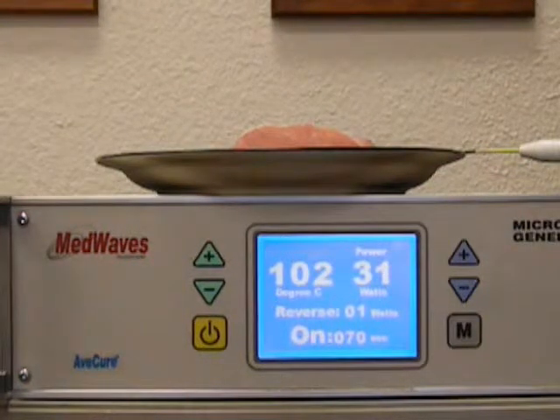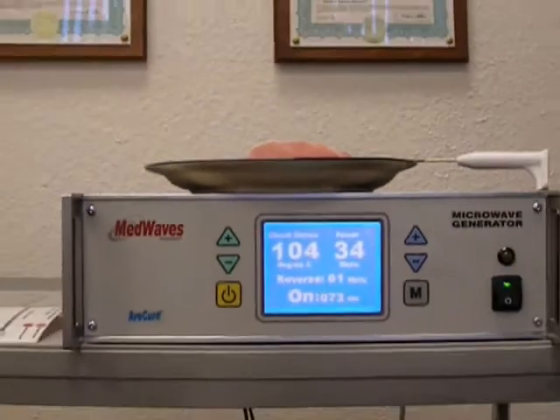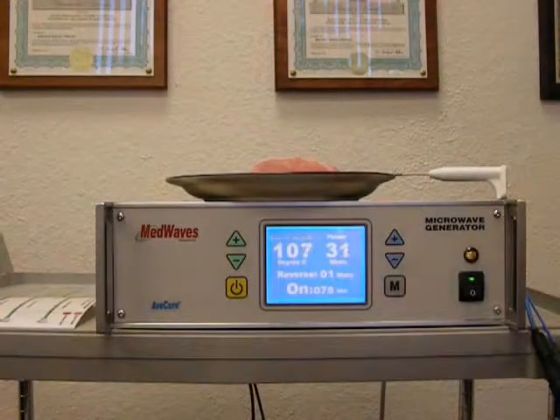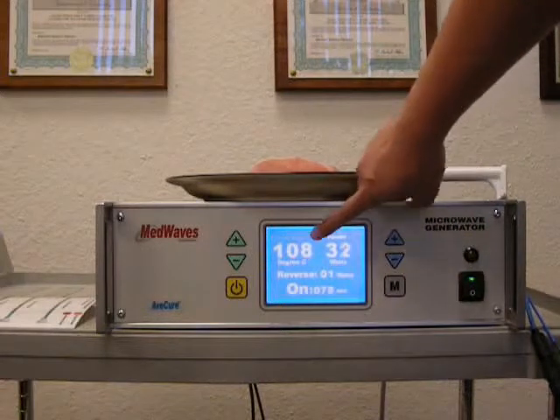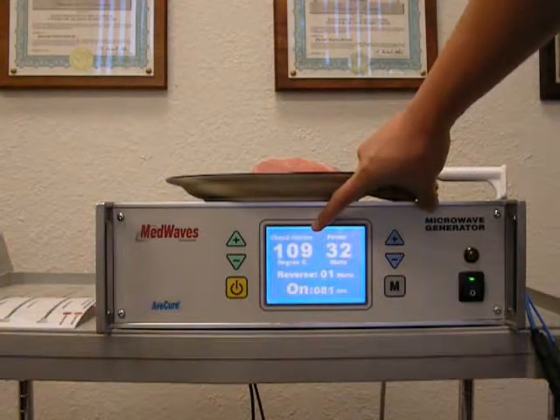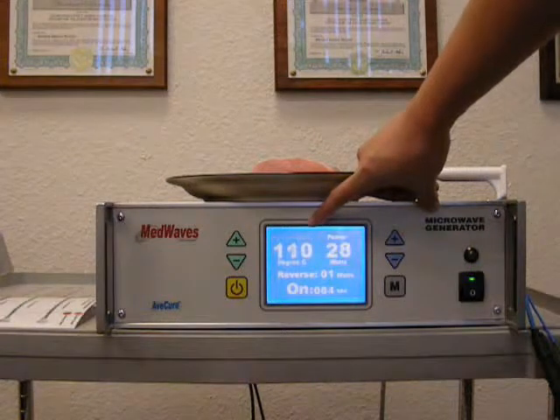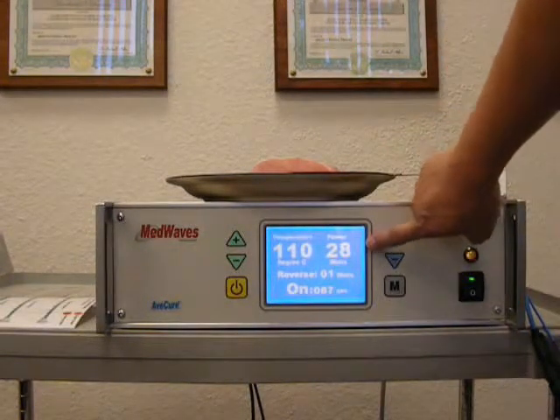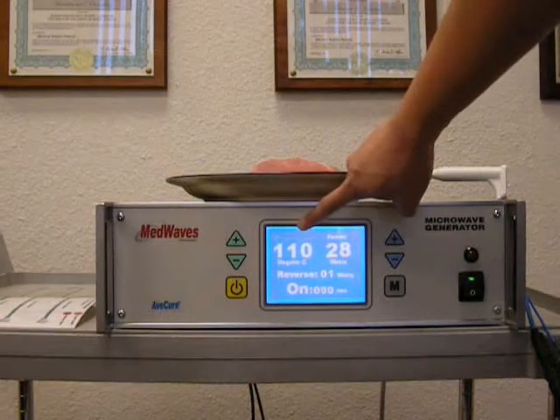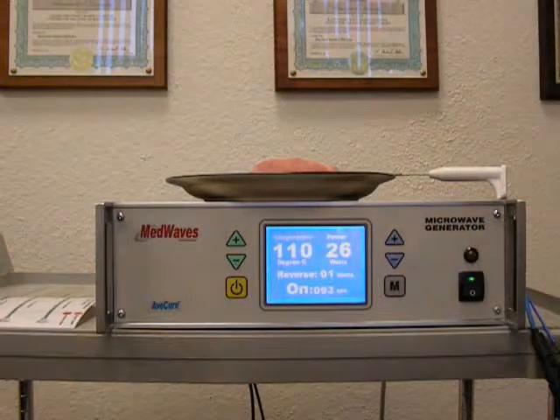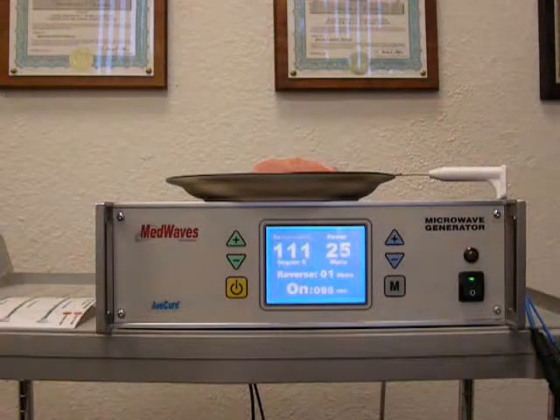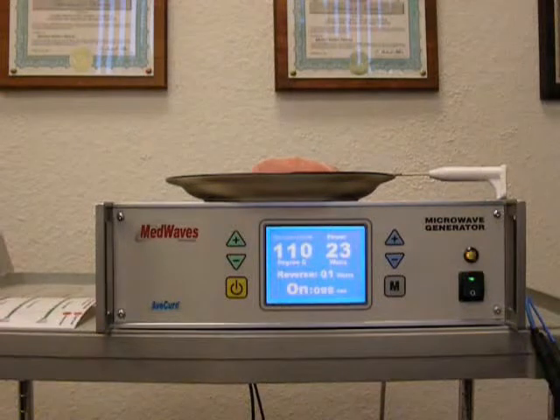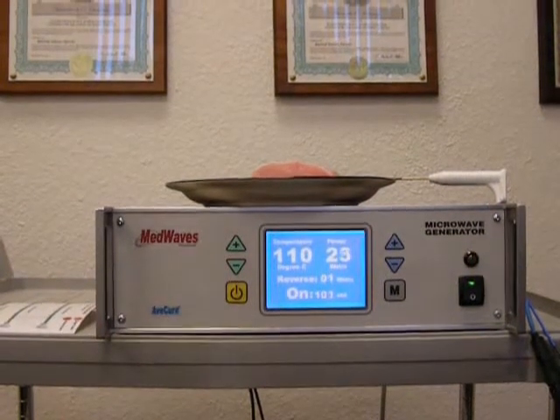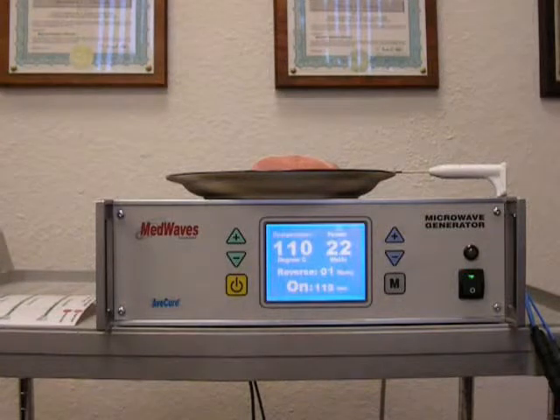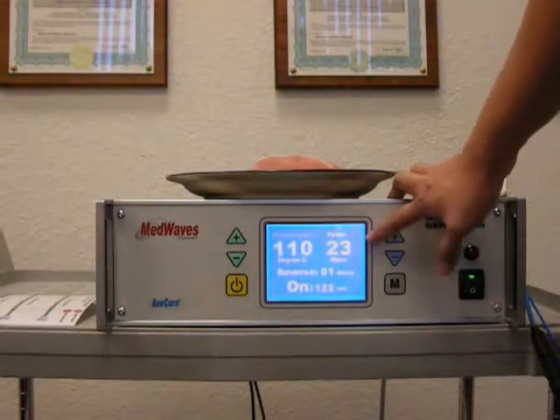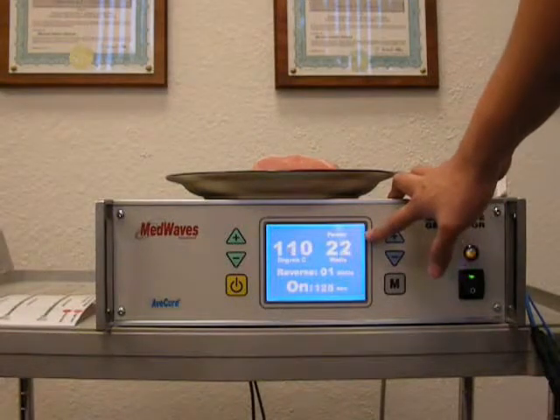This yellow light indicates the ablation is on, right here. As you can see, the temperature is reaching the target temperature. Once it reaches that temperature, the power will modulate to keep the temperature at the desired setting. In temperature control mode, if the power drops below 20 watts, the generator will automatically switch to power control mode.